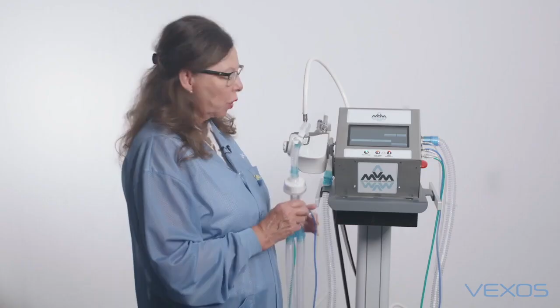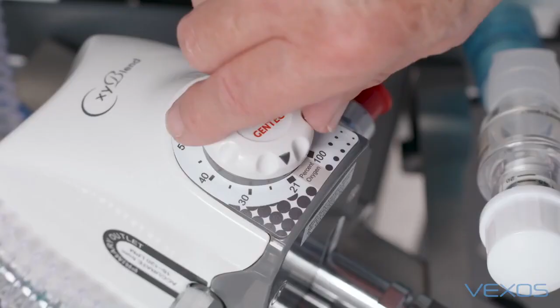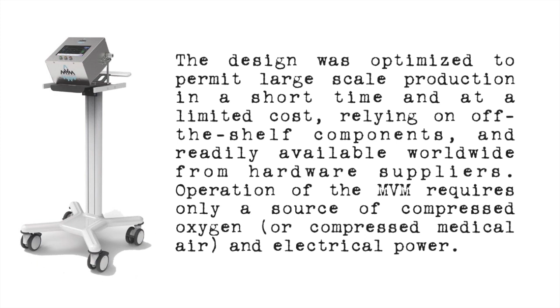The MVM project was born out of the need to ensure ventilator access for those who need them during the COVID-19 pandemic. One way of meeting this need is increased production of high-capacity, moderate-cost ventilators, a design specification met by the MVM that is way cheaper than typical high-end intensive care unit equipment. The MVM is designed to meet the requirements of a ventilator as simply as possible. The design was optimized to permit large-scale production in a short time and at a limited cost, relying on off-the-shelf components readily available worldwide from hardware suppliers. Operation of the MVM requires only a source of compressed oxygen or compressed medical air and electrical power.